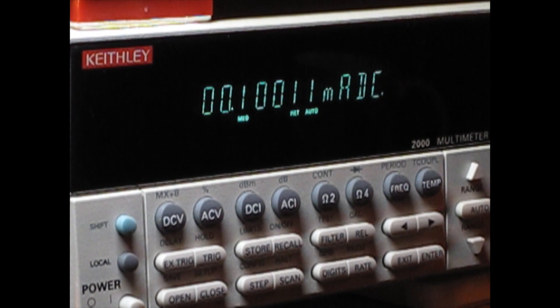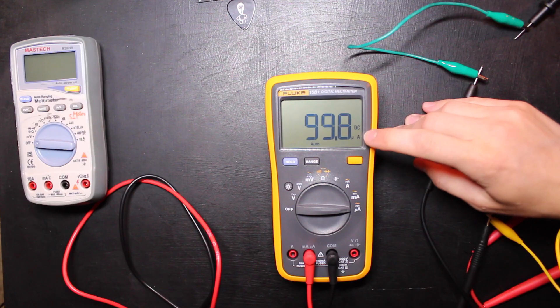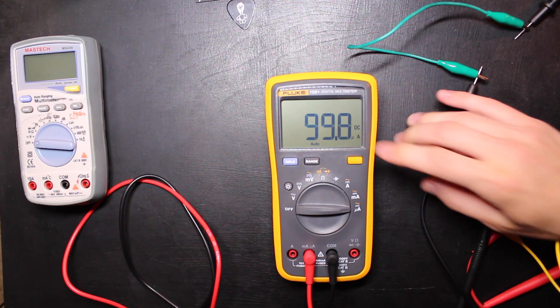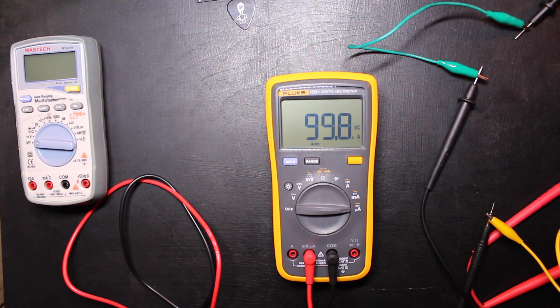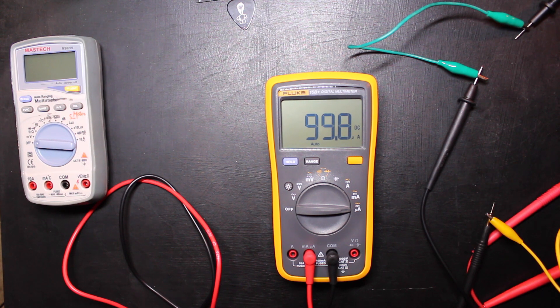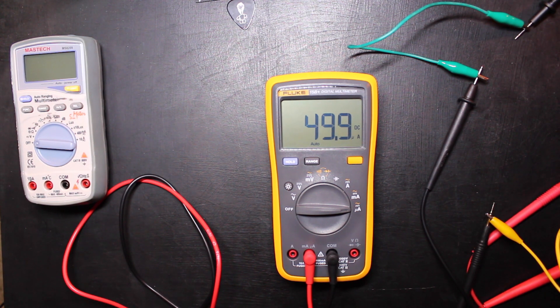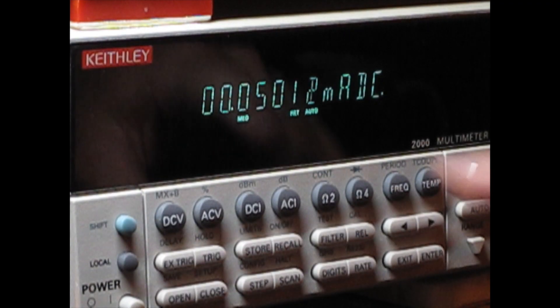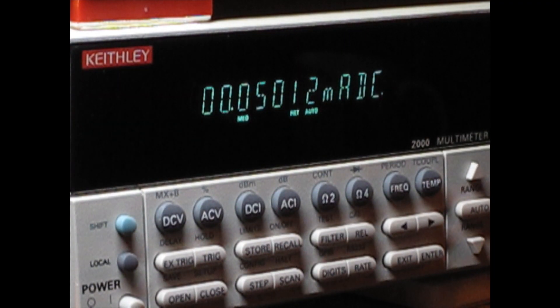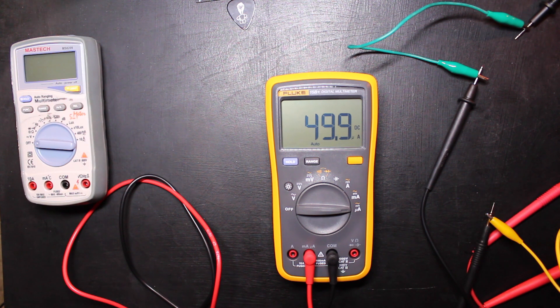So this is 100 microamps—so this is 100.11 microamps and we've got 99.8 microamps here on the Fluke. So let's keep dropping that and see what happens. Okay, so there's 50 microamps, we're getting 50.12 there, 49.9, so that's pretty good.